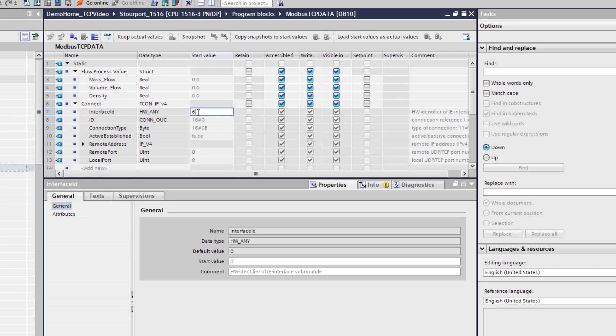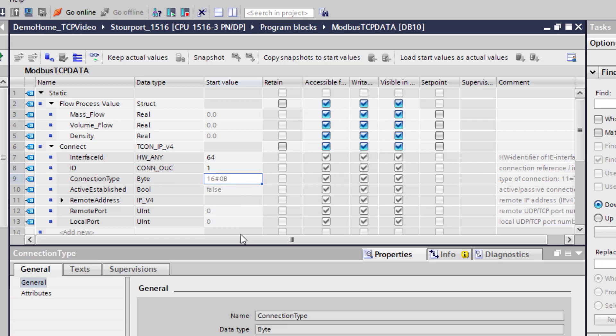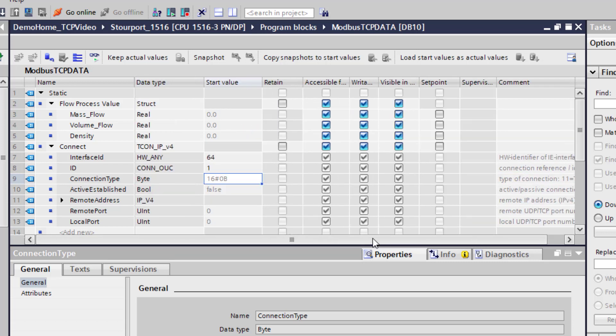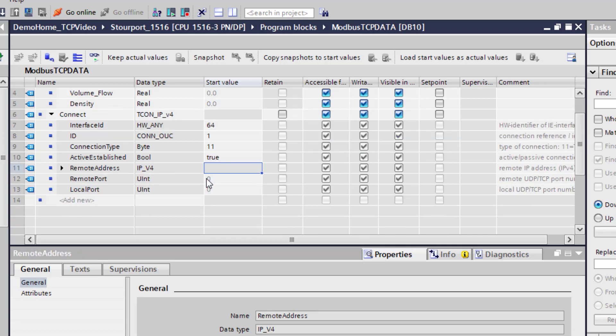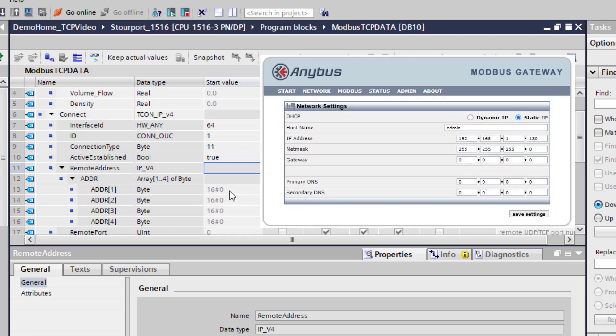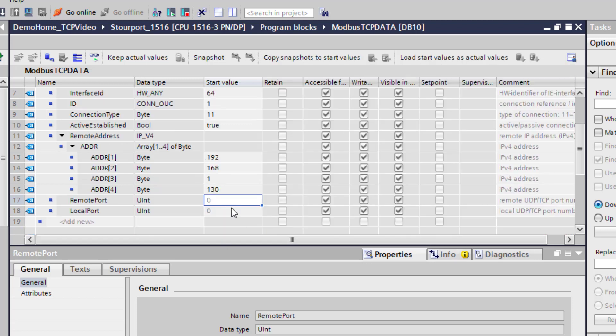And then the next one is purely an identifier for this function because you may be reading more than one server or connecting to more than one server. So we give that a 1. And then over here your connection type - you can see 11 TCP, that is us. So 0B is 11 anyway but we will put that in. And then establish connection - so this is whether it is a client or a server. If you get it wrong the error code sort of leads you to tell you that you have got it wrong. But that needs to be true. And then we come to the information for the server itself. So we have the address, and this is your IP address split into 4 bytes. And this is the IP address of the server.